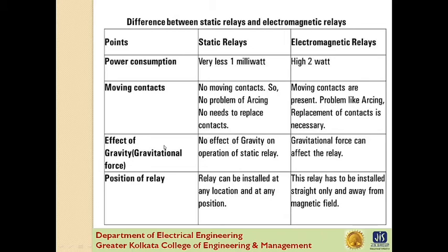Effect of gravity, gravitational force: there is no effect of gravity on the operation of static relay. Gravitational force can affect the electromagnetic relay. Position of relay: static relay can be installed at any location and any position. But electromagnetic relays have to be installed straight only and away from the magnetic field.